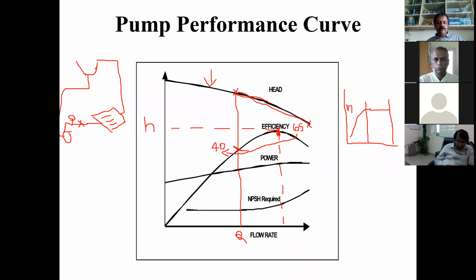So when it comes to a pumping system, we need to bank on some measurements. We need to measure the power, we need to measure the flow rate, we need to measure the pressure, discharge pressure, suction pressure. So these are some of the basic ingredients that go into the audit of the pump systems. And the third curve, what you have here is the power curve. So the power, as you can see, keeps on increasing. The more the flow, the more will be the power. So these are the three most important curves that come along with the typical pump as it is sent by the manufacturer. Then there is another requirement from the operational point of view, which is NPSH. Will not go into it in this session.